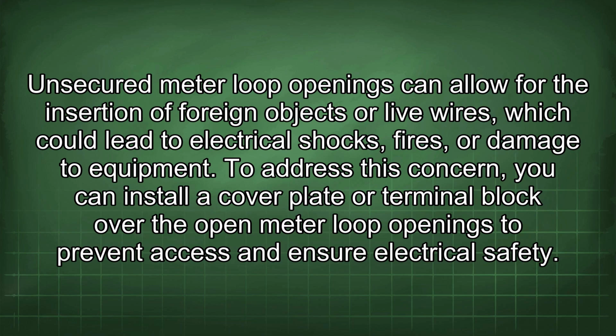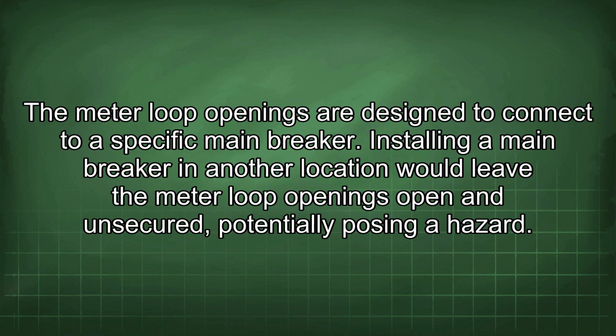To address this concern, you can install a cover plate or terminal block over the open meter loop openings to prevent access and ensure electrical safety. The meter loop openings are designed to connect to a specific main breaker. Installing a main breaker in another location would leave the meter loop openings open and unsecured, potentially posing a hazard.